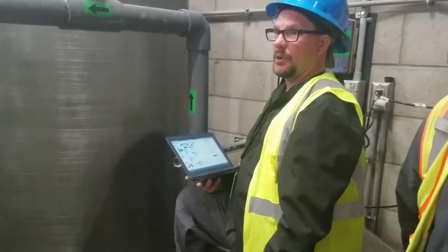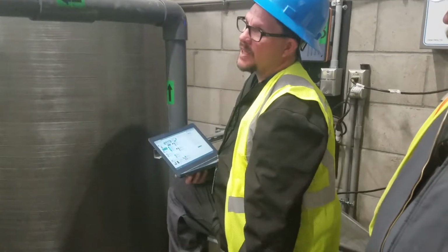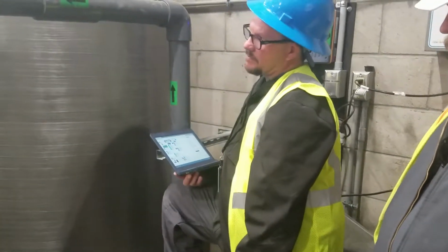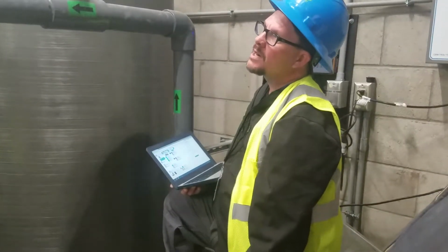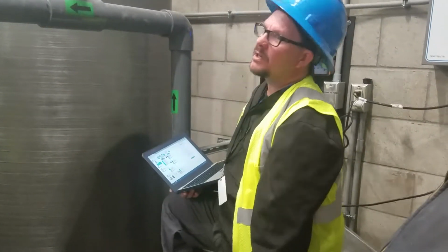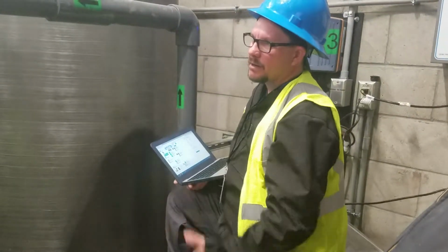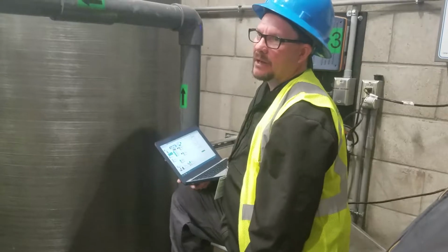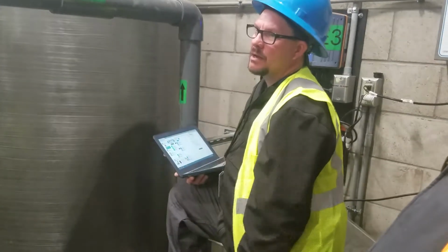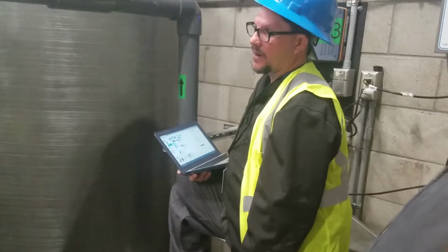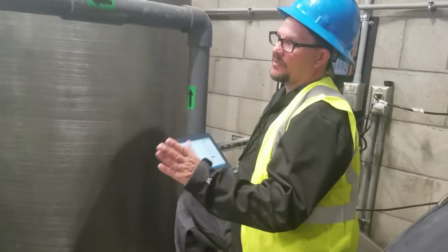whatever we're putting in. I just did the Palm Springs Aquatic Center. They came off of LMIs because of the maintenance and the cost involved, and they installed 4. I had to put 4 M170 DM5s in, dual head, capable of getting 170 gallons of chlorine in a 24-hour period per head. And they have a 1,000-gallon tank down there.